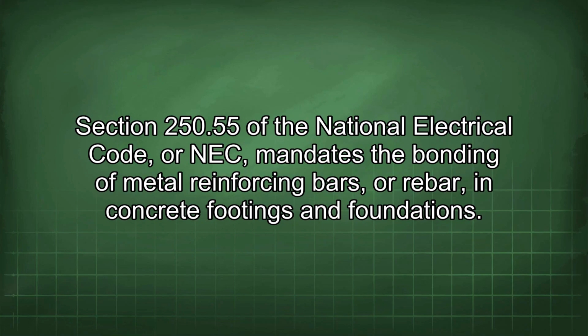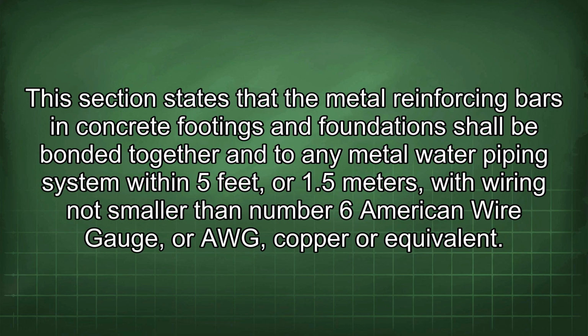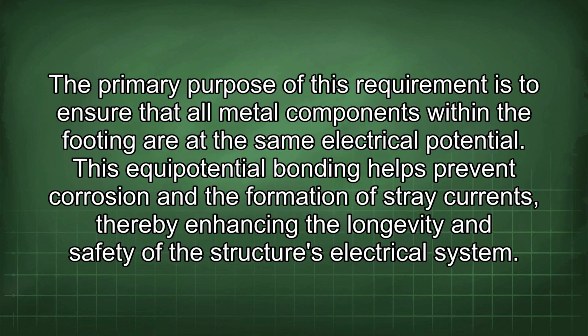250.55 of the National Electrical Code, or NEC, mandates the bonding of metal reinforcing bars, or rebar, in concrete footings and foundations. This section states that the metal reinforcing bars in concrete footings and foundations shall be bonded together and to any metal water piping system within 5 feet, or 1.5 meters, with wiring not smaller than number 6 American Wire Gauge, or AWG, copper or equivalent. The primary purpose of this requirement is to ensure that all metal components within the footing are at the same electrical potential. This equipotential bonding helps prevent corrosion and the formation of stray currents, thereby enhancing the longevity and safety of the structure's electrical system.